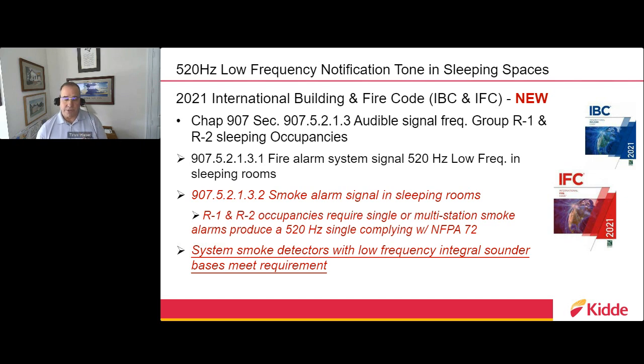The unfortunate part today is that there isn't a manufacturer providing a smoke alarm, that 120 volt AC with battery, available on the market that produces that 520 hertz signal. Now, this is not a retroactive code, and this code will only be enforced where the local AHJs have passed the code and it is available for them to enforce. So typically that would probably be about 2 to 3 years down the road, but there could be certain jurisdictions that enforce it today.